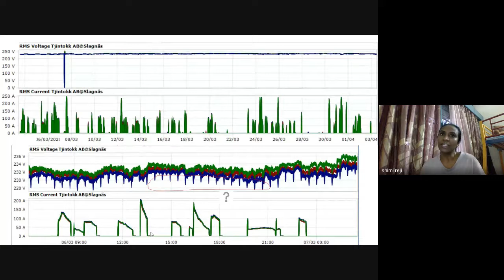These were the different patterns we identified, and the third harmonics of all the cars, around 90 cars charging. We found that it's not only the background harmonics, but during charging these harmonics are also present. This is the fifth harmonic, this is the seventh harmonic, these are some of the eleventh harmonics.